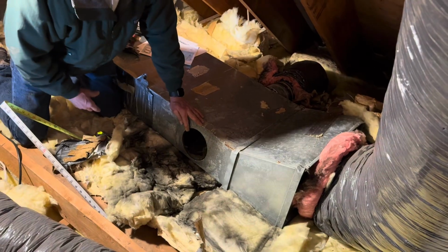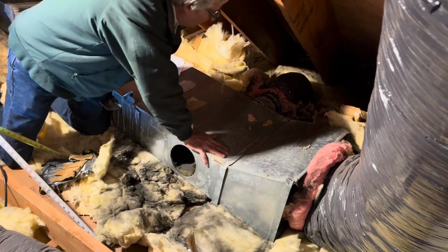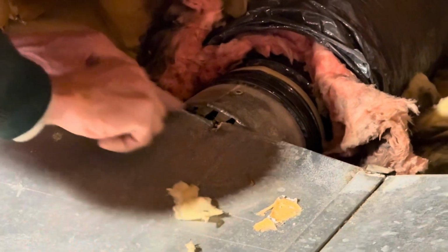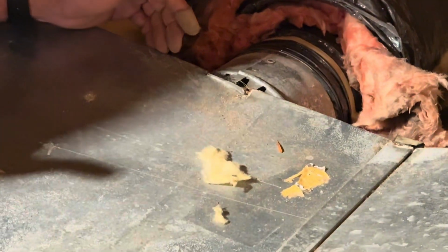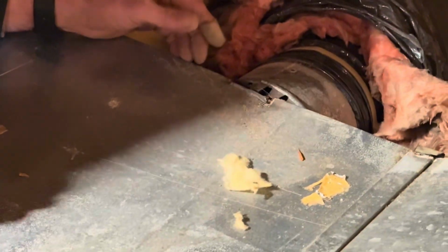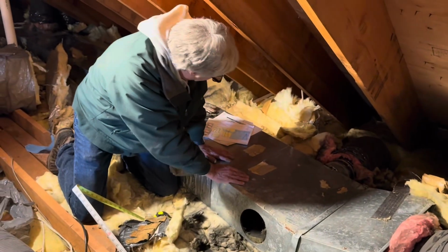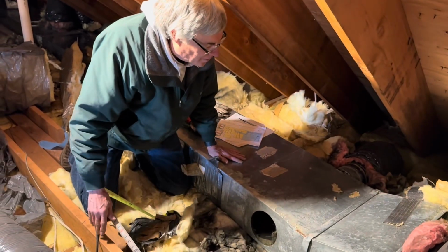Another thing that's bad here is that somebody used a really poor duct connection. And that duct connection actually fell apart over time, and it wasn't assembled very well. So we had a lot of leakage here that was going to the attic and not to the room. So the rooms could be cold or hot in the summer because they're not getting all the air that they were designed to get. So here are some of the things that we're going to fix.